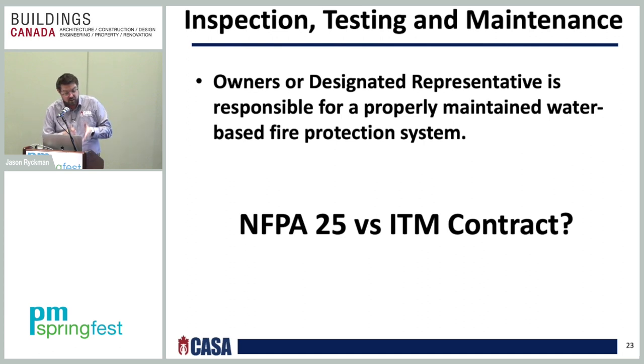Okay. Make sure that that inspection reflects that contract, that you only do dry sprinkler systems on that water-based fire protection system. One of the main contracts that you'll see out there is one-year annuals. So if you do an annual, you have to follow everything for your annual inspections. It has to marry with the contract, with the inspection forms.